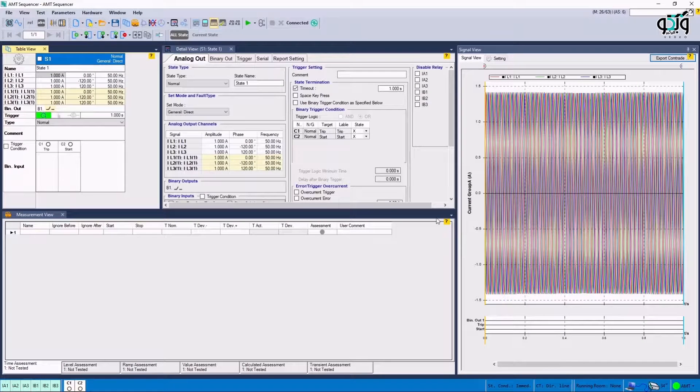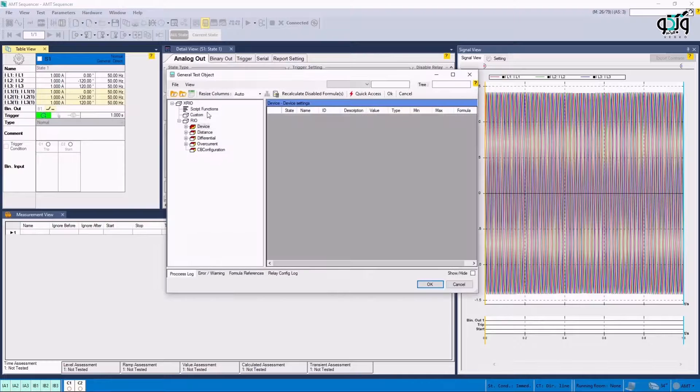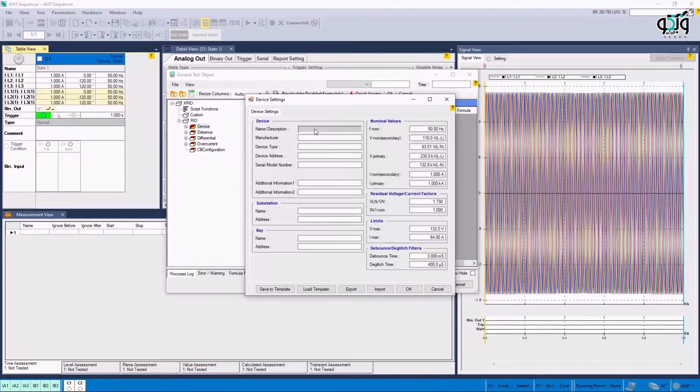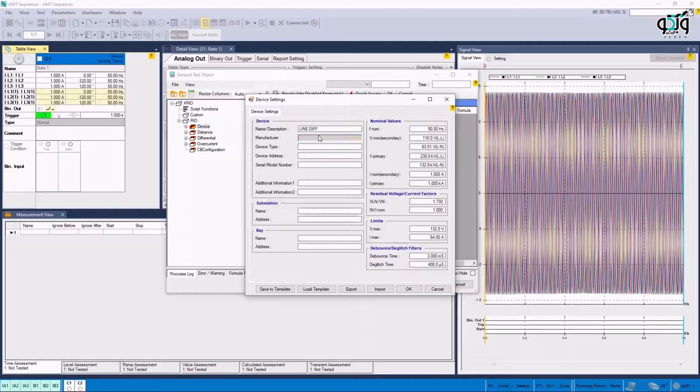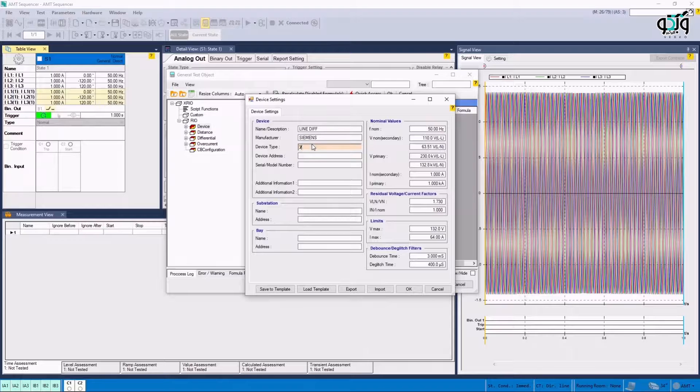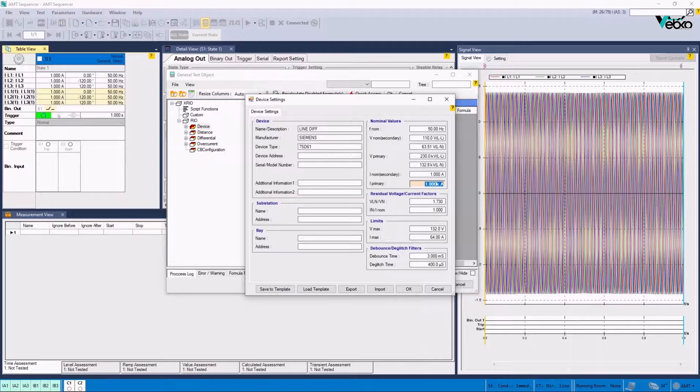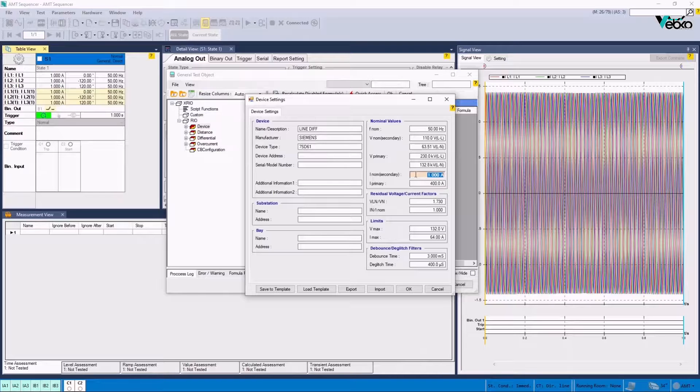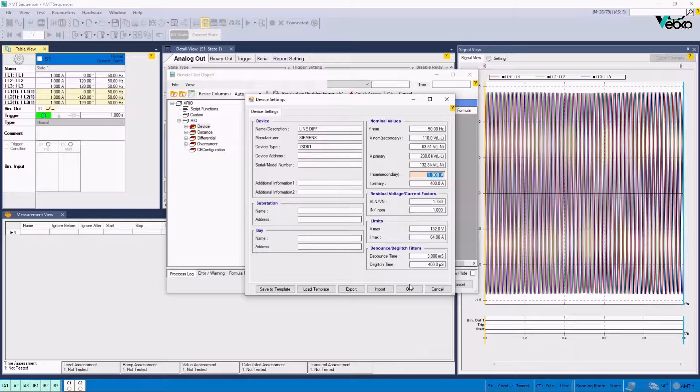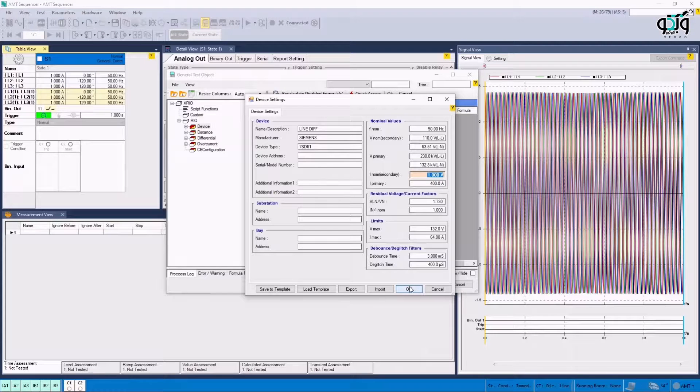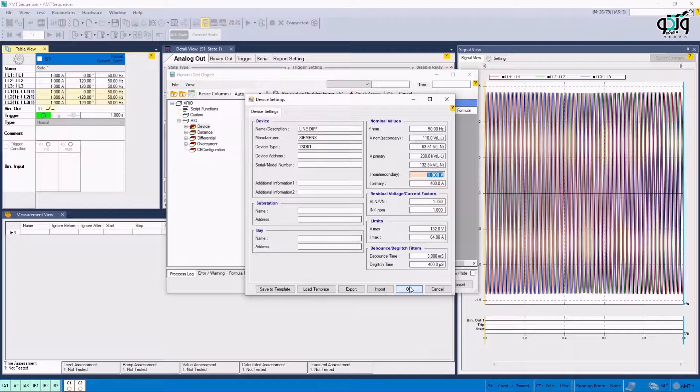By clicking on Test Object Parameters and then clicking on Device, it is possible to enter information about the test such as the title of the test, the manufacturer company, the relay type, the primary and secondary voltages and some other information that are needed in the report. It should be noted that it is possible to add the information related to the rows at the left side of this window after performing the test but the information related to the rows on the right side must be specified before initiating the test.